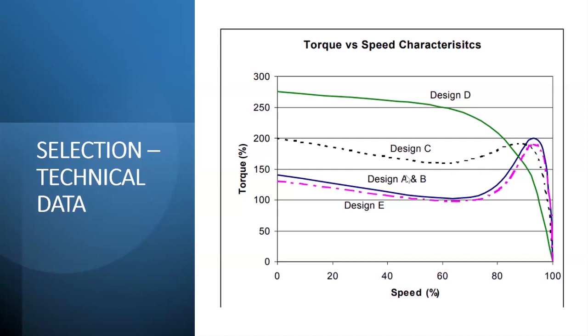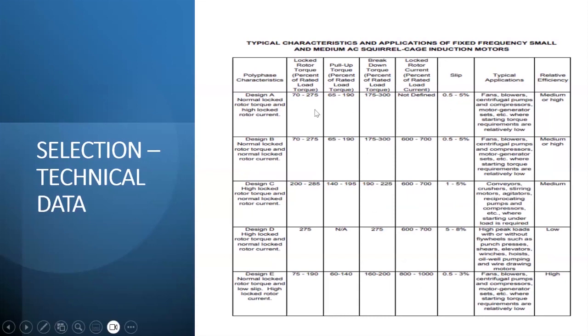So if you do not specify and choose the correct motor, you will have a lot of maintenance issues, a lot of trips. So your starting frequencies will increase. And when the starting frequencies increase, chances are that the motors will overheat. And when the motors overheat, it will get insulation failure and the motor fails. This chart shows typical examples of design type and their application. Let's look at the design type C, for instance. You can see that it's used for conveyors, for crushers, for stirring motors, agitators, reciprocating pumps, compressors, and so on. So based on the application, you must select your design type. Else, manufacturers will manufacture your motor according to design type B, and you will have a lot of issues in your operation.